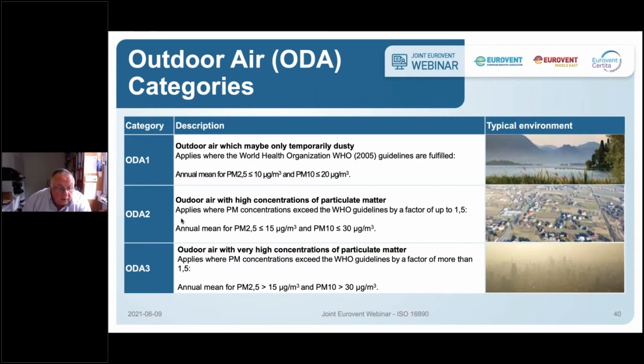Then when the outer air quality is worse, there's more dust in the air, these factors are just multiplied by the factor 1.5. And for the worst outer air quality, these factors are multiplied by a value more than 1.5. You see here that's a mega city with a lot of smoke. If there is an annual mean of PM2.5 larger than 15 microgram per cubic meter, in that case an outdoor air quality 3 should be chosen. So that's the first step. Outdoor air quality is chosen according to the location of the building.